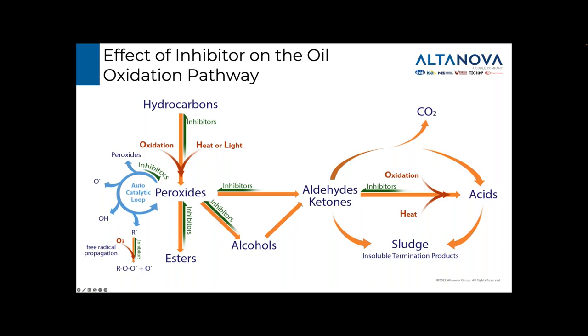the chance of overheating. Inhibitors are sacrificial molecules that prevent or reduce the speed of reactions by attacking the reactive components in the oil that form as a result of the oil breaking down in service. They are essential for the longevity of the oil in service. All oils will have some inhibitor in them. However, most oils come with natural inhibitors, which are undeclared. But many oils, like Shell's gas to liquid oil or GTL, are dosed with a synthetic inhibitor like DBPC or ditertiary butyl-paracresol, and these are called declared additives.